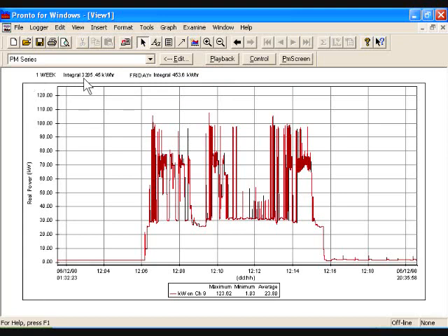And so 1 week was 3,200 kilowatt hours. Friday was just 453. Now, they look kind of lazy here on Friday. Not a lot of work being done where they had a lot of shutdown time, probably because of the problem we discussed on that microprocessor shutting the machine down.